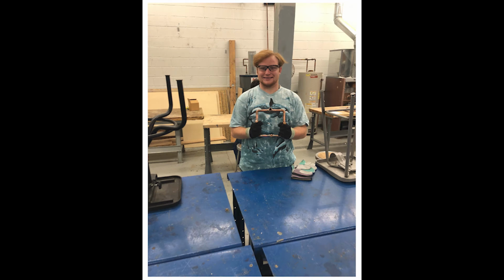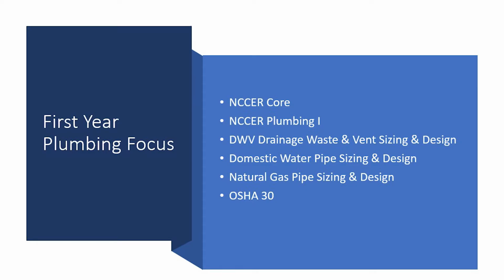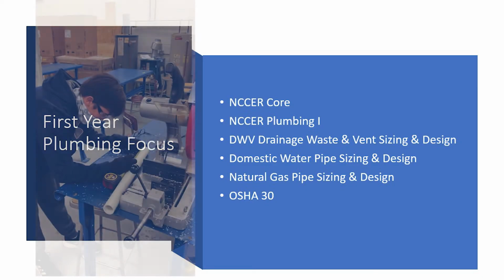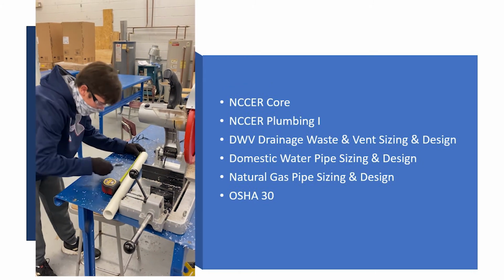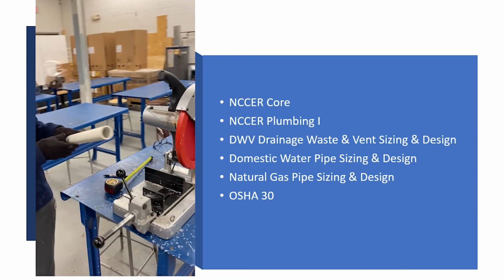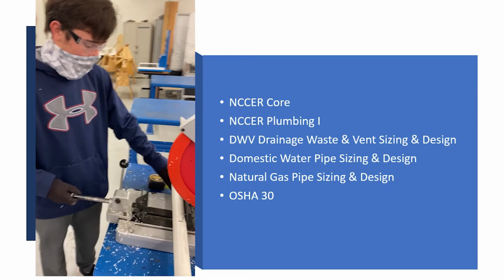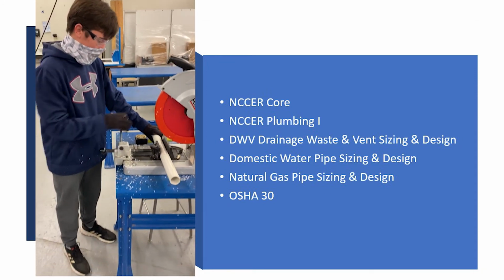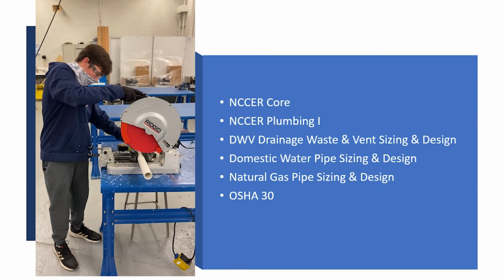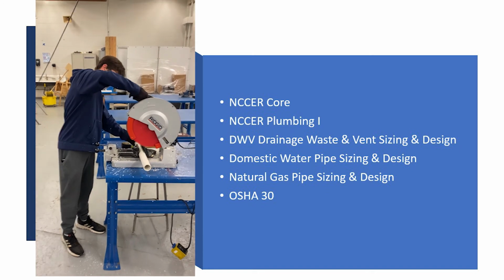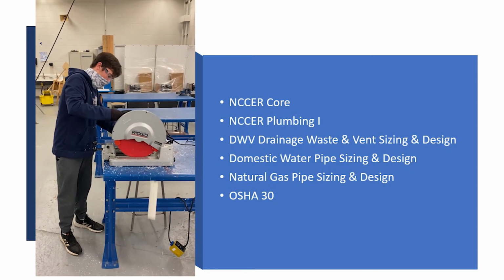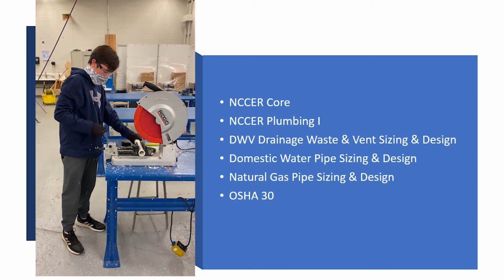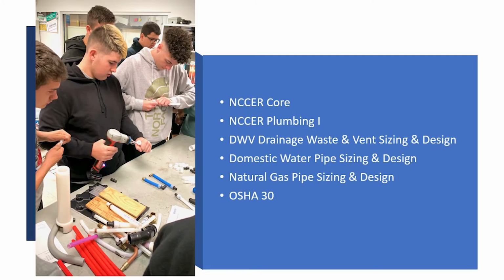We also do a lot of design work. In their first year, they'll be designing drainage, waste, and ventilation systems, which means sizing all the pipes. So if you had 2 or 3 bathrooms, what size would you need? We also get into domestic water pipe sizing. If you had a house with 6 bathrooms and 2 kitchens, what size cold or hot water line would you need? It's actually more based on the velocity that the water will be traveling in the pipes, so we use some specialized software for that as well.